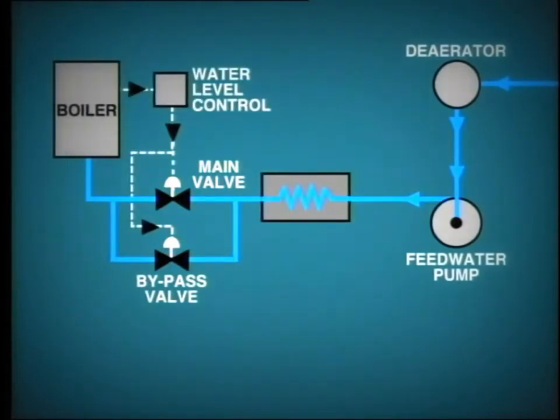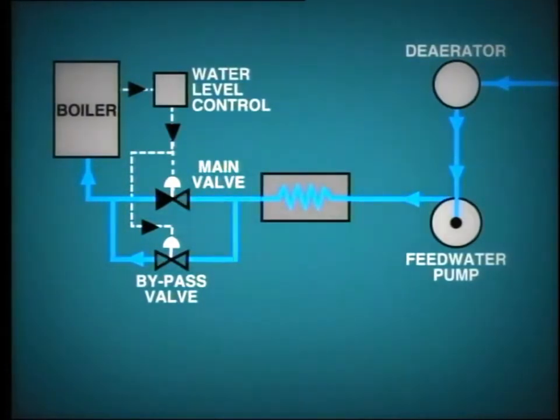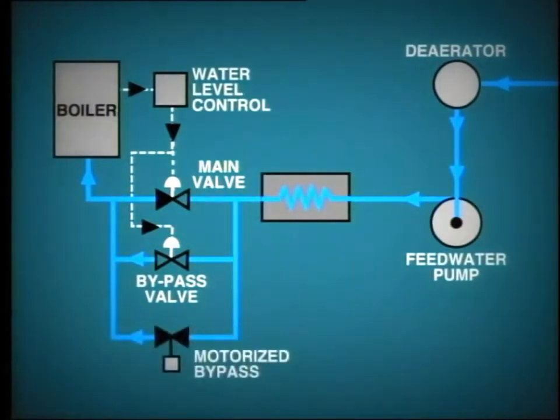During startup and at low load, the small control valve is operated. Eventually, as load increases, this valve approaches the full open position and the large valve takes over the operation. A further bypass may be fitted around both of these valves for use in case of failure of the boiler control system or valve actuators.